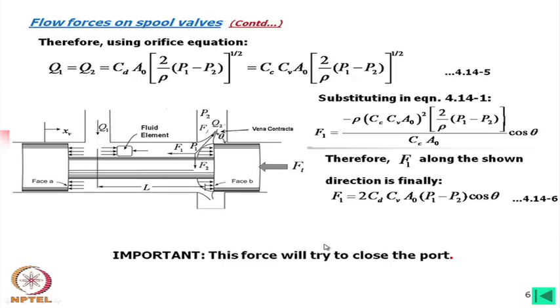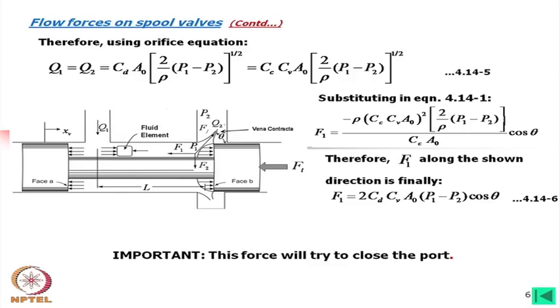This means that while opening the port by pushing the spool to the right, we must apply force from left to right, but the flow force opposes that — it acts to close the port. If we release the spool, it would automatically close. This means the steady state flow force helps in controlling the valve.